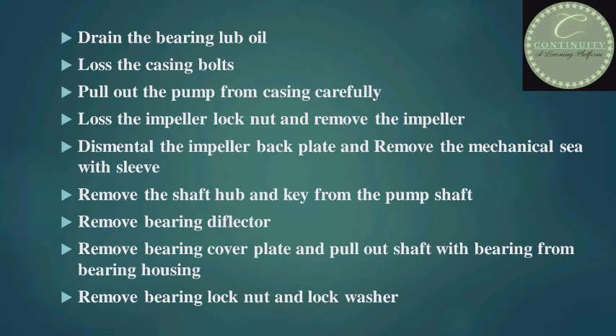Drain the bearing lube oil. Loosen the casing bolts and pull out the pump from the casing carefully. Loosen the impeller lock nut and remove the impeller. Dismantle the impeller back plate and remove the mechanical seal with sleeve. Remove the shaft hub and key from the pump shaft. Remove the bearing deflector. Remove the bearing cover plate and pull out the shaft with bearing from the bearing housing.